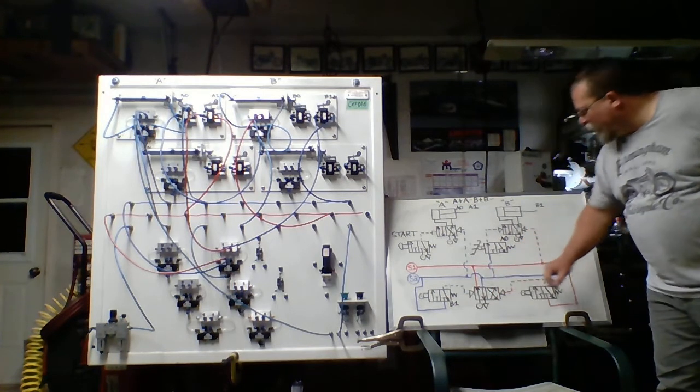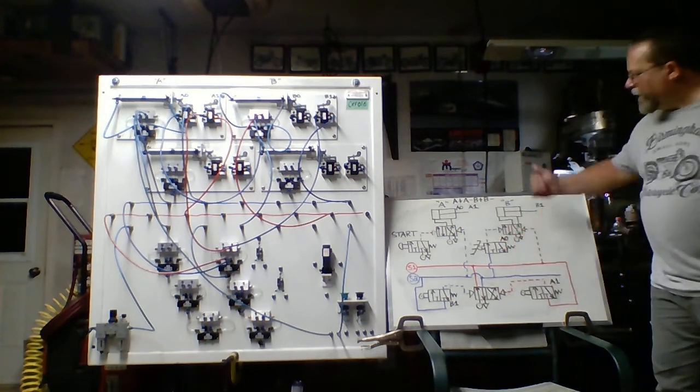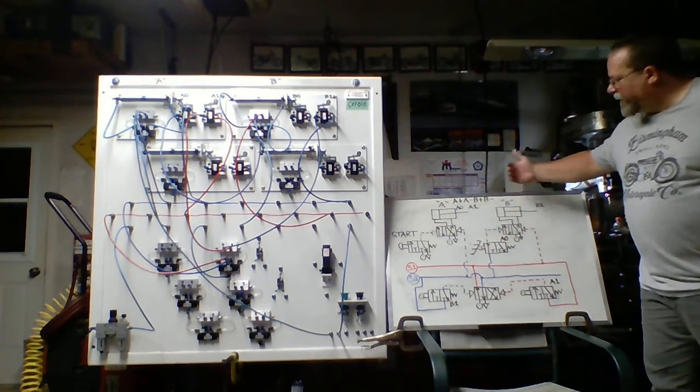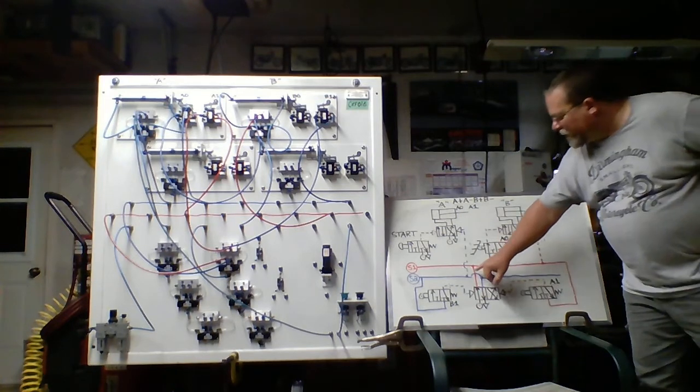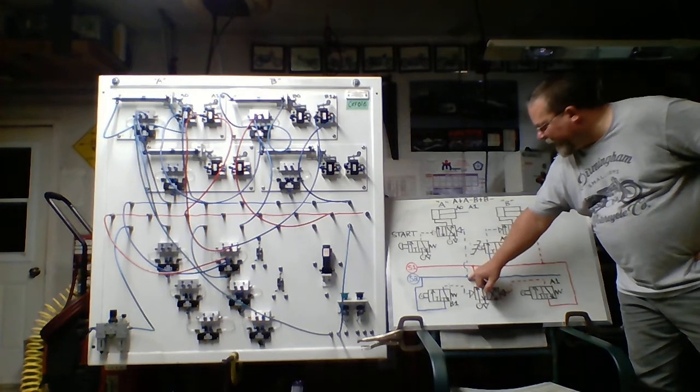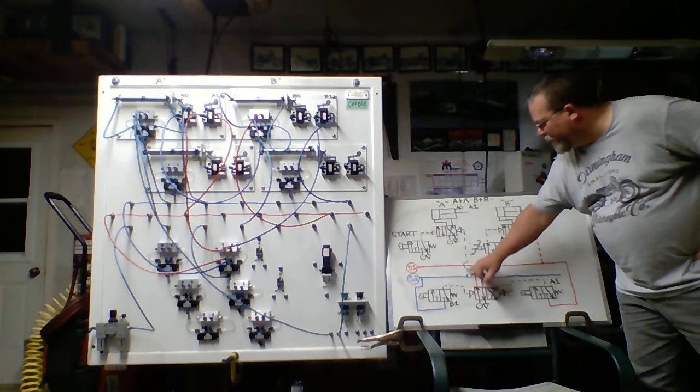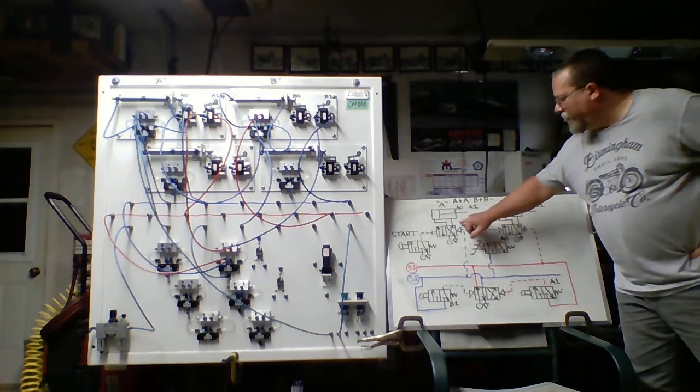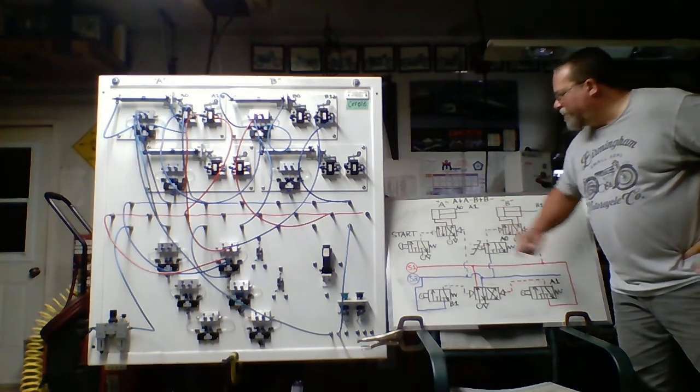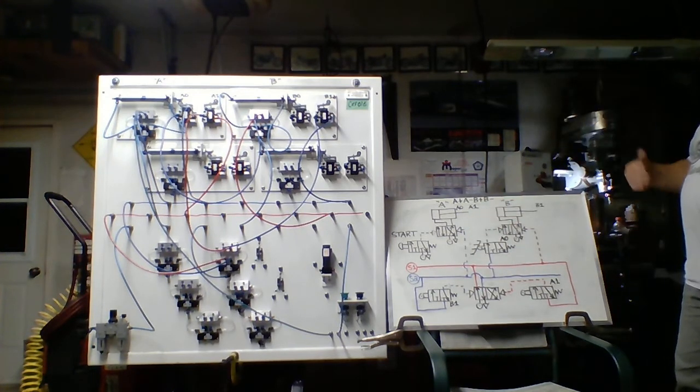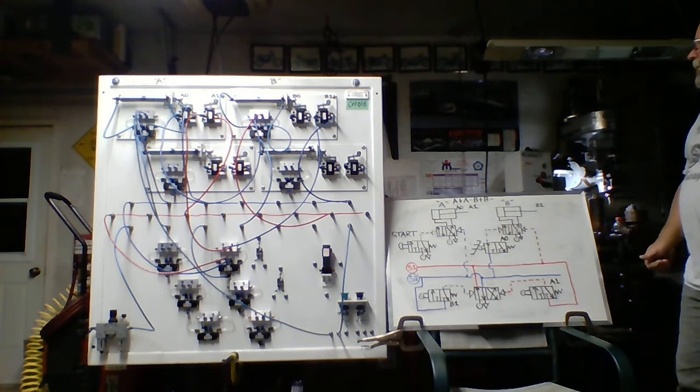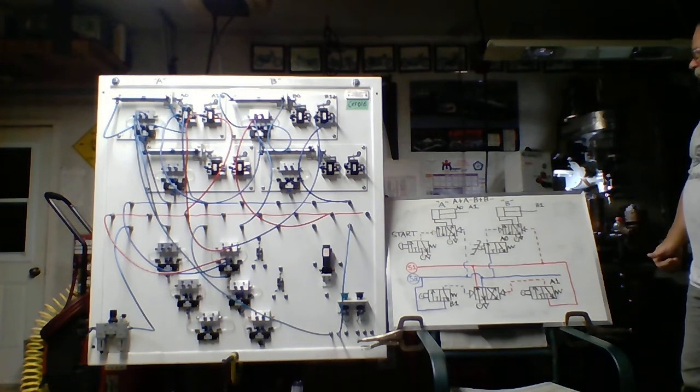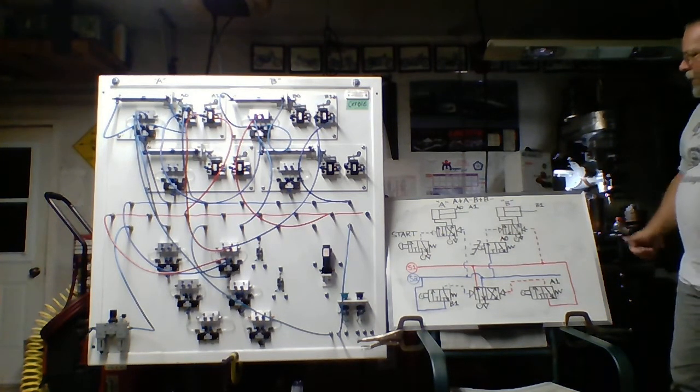So when we shift the cascade valve and we have energy at source 2, what will happen? In this case, because of our order of operation, we want A to retract. Source 2 is plumbed directly, as indicated by that node, to your 4-2. It's going to shift that valve back in the home position and, of course, change the flow path, have A retract. When A retracts, it's going to get on A0.